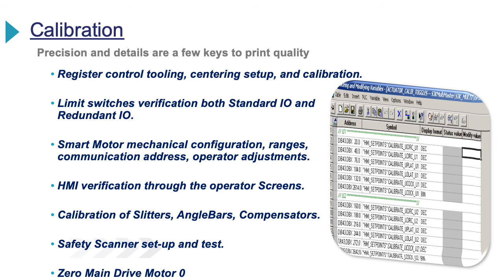Calibrated components. Again, depending on what you have for equipment, there is calibration needed on some of the modules. Registers, once they are reset or installed, must be calibrated, for the position is not broadcast by any type of encoder. Smart motors in some cases have soft stops built into the software to shut them down at their limits and need to be set up properly. Some of these can be done from the operator screen, where others have to be triggered manually in the PLC controller.